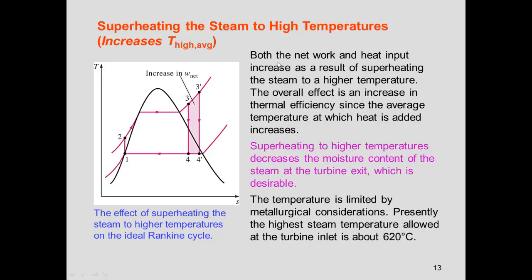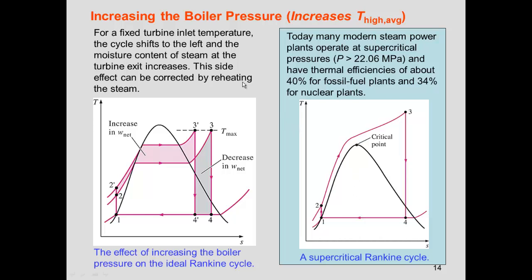Another way to increase efficiency is superheating the vapor to higher temperatures, moving from state 3 to 3 prime and adding the pink-shaded area to the net work. This temperature increase is limited by metallurgical considerations — the maximum currently achievable in turbine and boiler materials is about 620°C. If we fix the maximum temperature and increase the boiler pressure to state 2 prime, we gain the pink area but lose the gray-shaded area, with the net trade-off being positive.